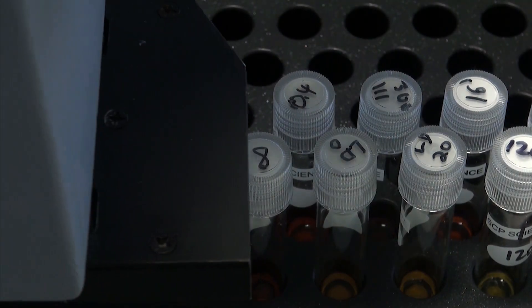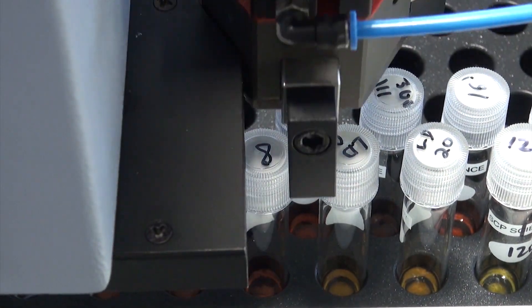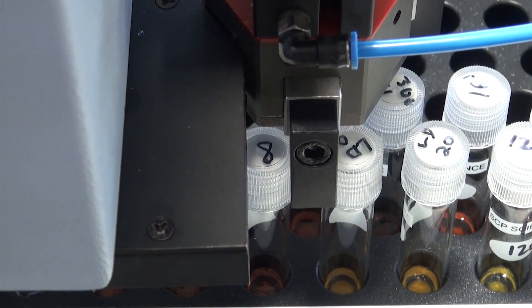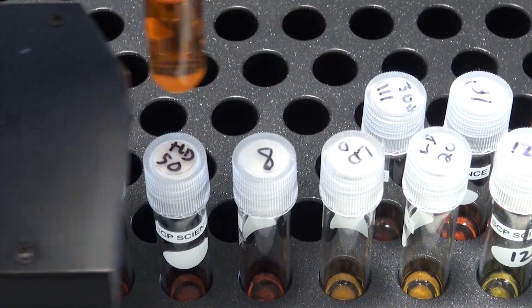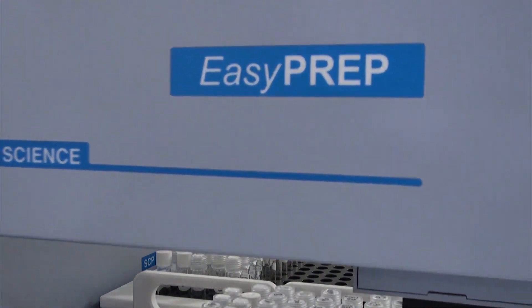EasyPrep COD 200 helps to increase productivity in the laboratory. There is a sensor adjacent to the gripper mechanism to verify the COD tube is in place prior to moving.